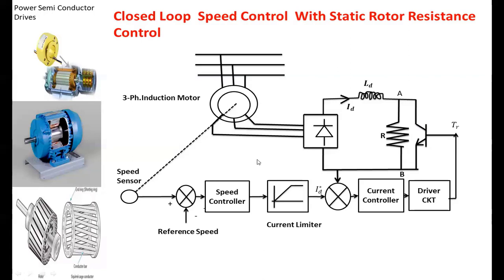This method can be applied only to the slip-ring induction motor; it cannot be applied to the squirrel cage induction motor because it does not have any provision to access the rotor terminals. Suppose we set some reference speed and the actual speed is less than the reference speed — the error in speed becomes large, the current limiter saturates and sets a maximum value. The driver circuit applies the base voltage to the BJT such that the DC link current equals the reference DC link current, maximum torque is generated, and the motor accelerates. The error in speed decreases, then the current limiter adjusts the reference DC link current so that the actual torque equals the load torque and the motor speed equals the reference speed.